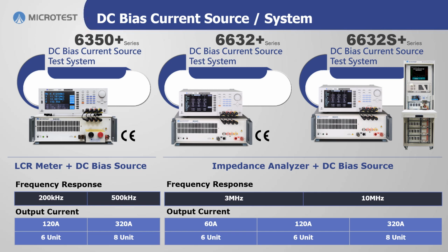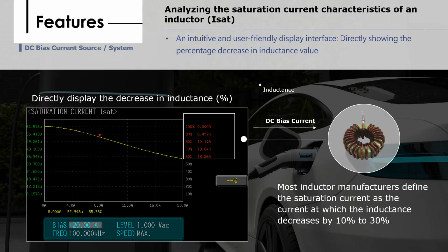For the high-frequency segment, we provide the 6632 Plus and 6632S Plus series, primarily consisting of an impedance analyzer with a built-in DC bias current source. The frequency response can go up to 10 MHz, and the maximum bias current output is 320 amps. The system is designed for testing magnetic saturation and temperature rise current in inductors or magnetic components. But what is the Isat magnetic saturation current?